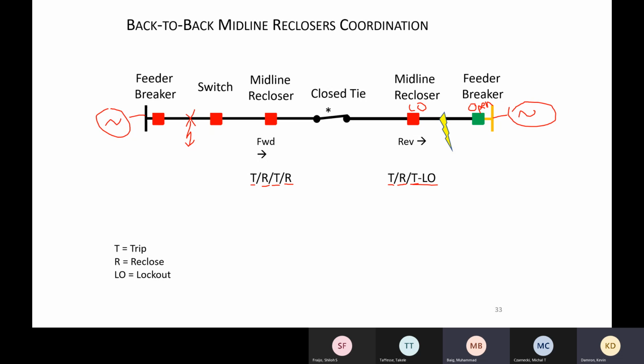Because we don't want to drop load, they'll come here, close this switch, and then open this breaker. Okay. So the time that takes them to close the switch and then open the breaker is the only time that you're technically a non-radial feed. I see. And the probability of a fault during that time is fairly low. Not that it couldn't happen, but we really haven't seen too many of those. Especially since our system operators have control of the switch and the breakers, so they can operate all of this remotely.